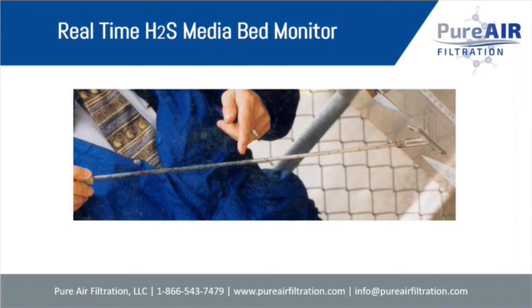And this rod starts off in this color. And then as the adsorbent media is consumed, our adsorbent media is consumed in a band from the inlet to the outlet. All right. This rod will actually change colors. This has been painted for dramatic effect, but it'll turn black. And as that rod, which is typically 3 feet long, gets blacker and blacker, you can pull that rod out and document once a month how much of the rod has progressively gotten black, and that will give you an indication of when you need to change it out.